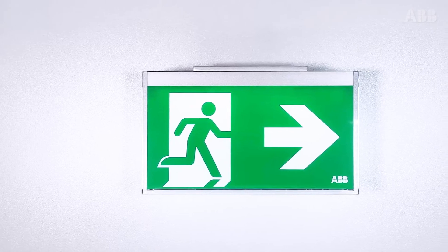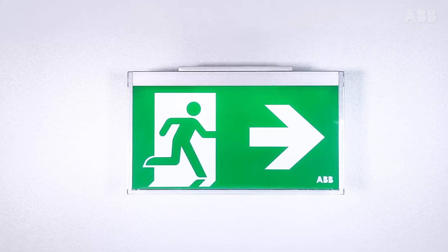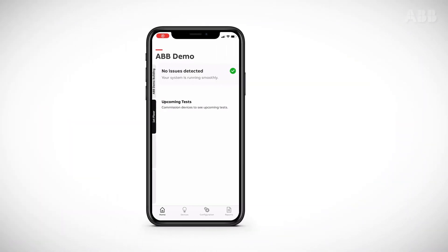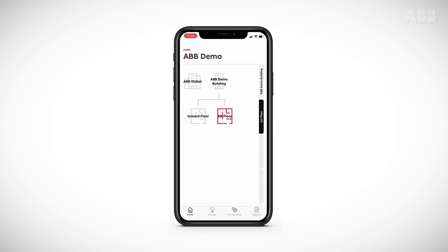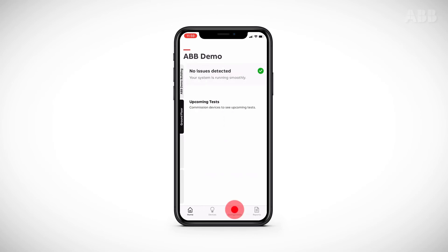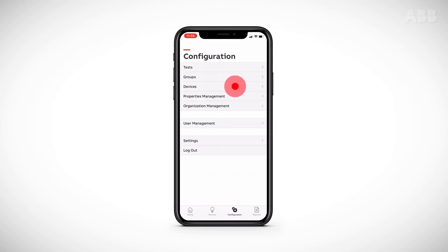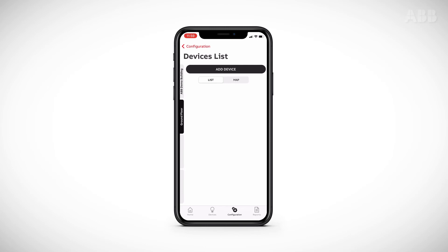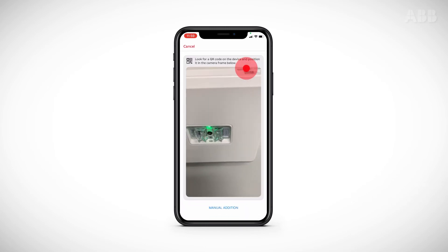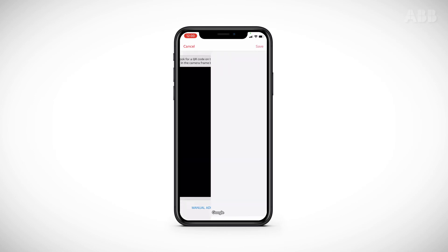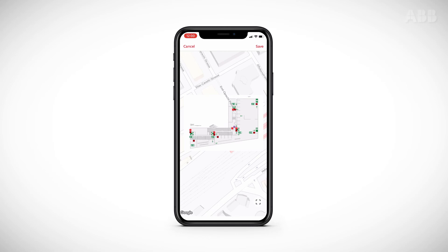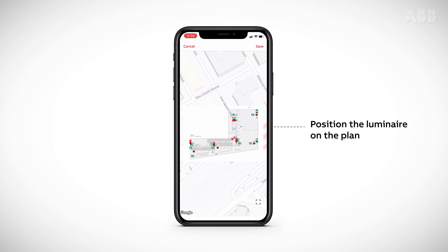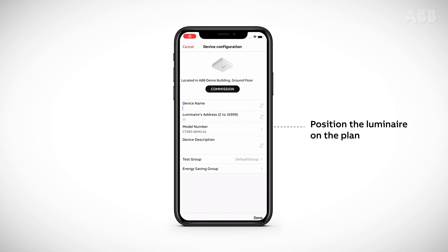Now let's look at how to add an emergency luminaire from the Navio Pro application. Addressable luminaires are added using the same commissioning procedure as Navio Pro gateways. From the application, select the desired building or level and then click on the Configuration tab and then on Devices. Continue by clicking on Add Device to activate your smartphone's camera. After scanning the QR code, and if a floor map has previously been loaded into the application, you have the option of positioning the luminaire on the map. Otherwise, the application moves on to the Device Configuration page.